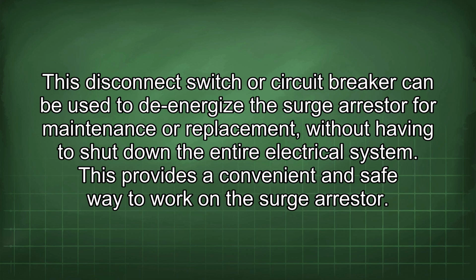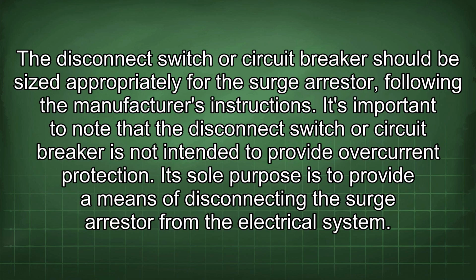to shut down the entire electrical system. This provides a convenient and safe way to work on the surge arrestor. The disconnect switch or circuit breaker should be sized appropriately for the surge arrestor, following the manufacturer's instructions. It's important to note that the disconnect switch or circuit breaker is not intended to provide overcurrent protection. Its sole purpose is to provide a means of disconnecting the surge arrestor from the electrical system.